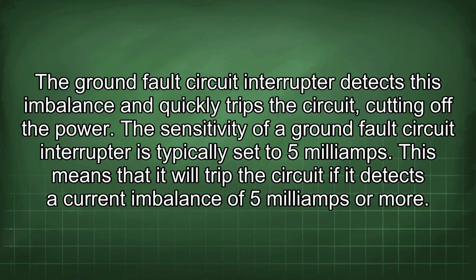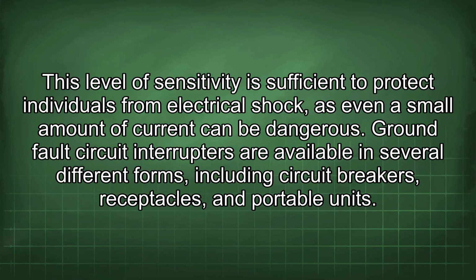The sensitivity of a ground fault circuit interrupter is typically set to 5 mA. This means that it will trip the circuit if it detects a current imbalance of 5 mA or more. This level of sensitivity is sufficient to protect individuals from electrical shock, as even a small amount of current can be dangerous.